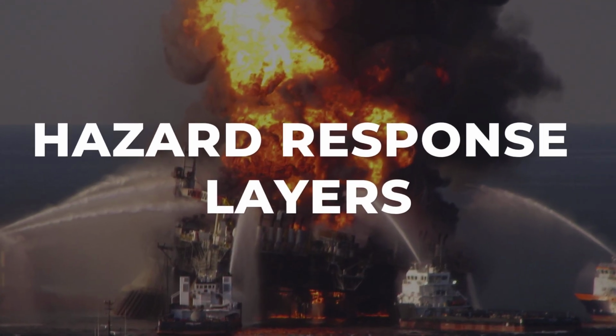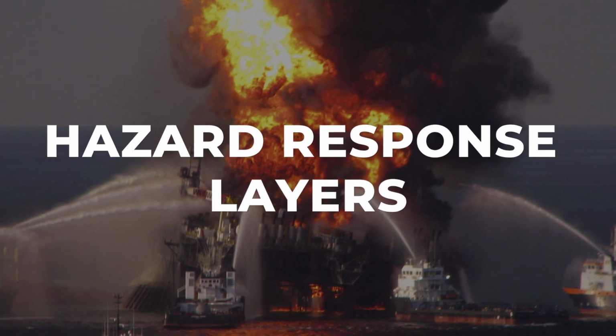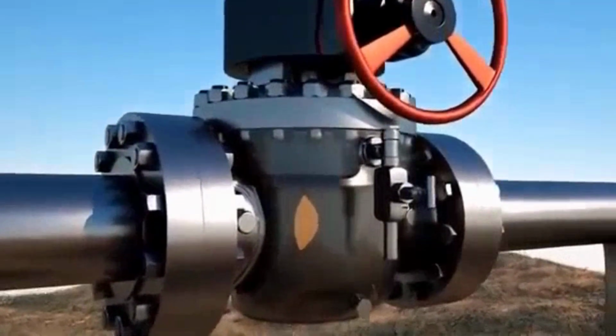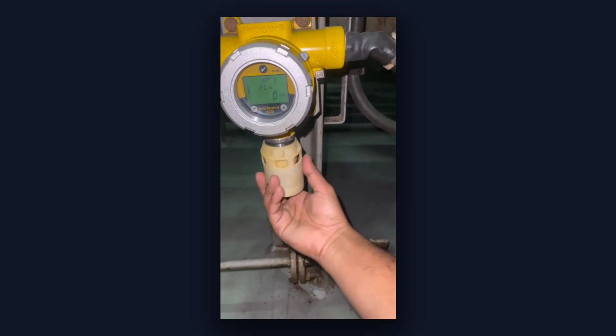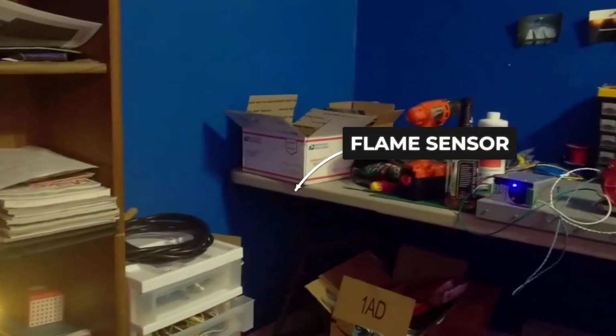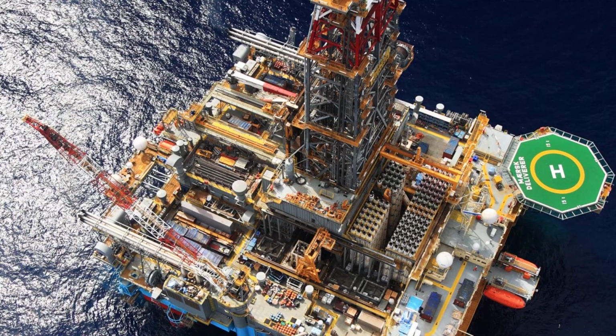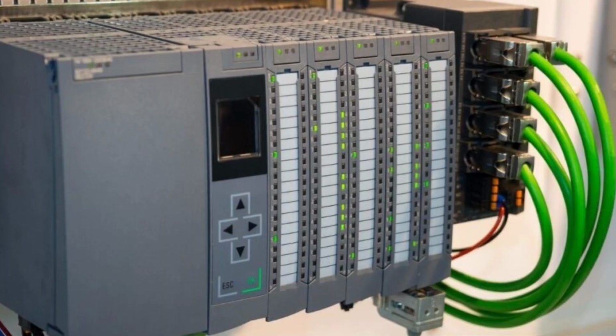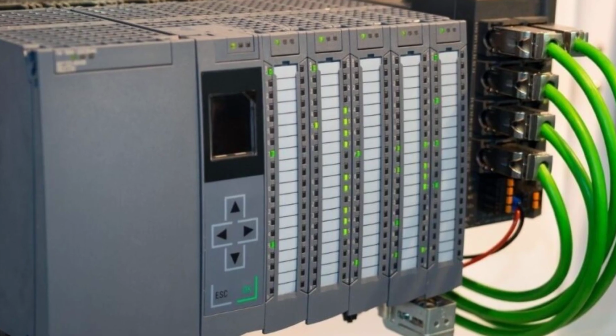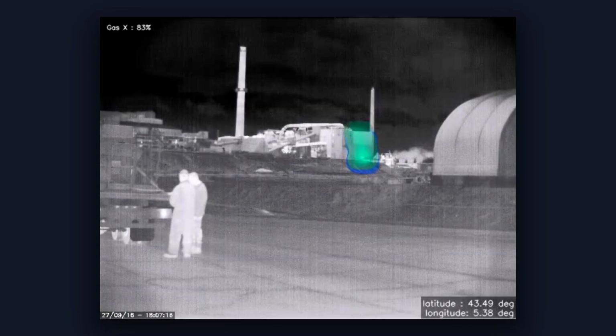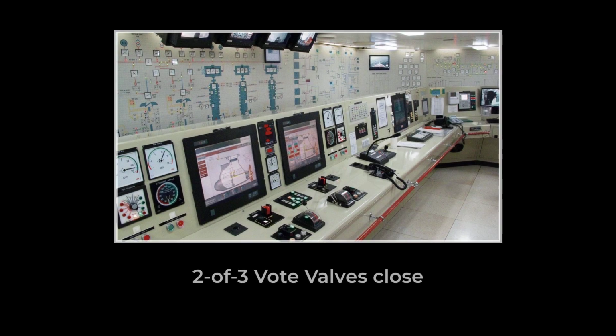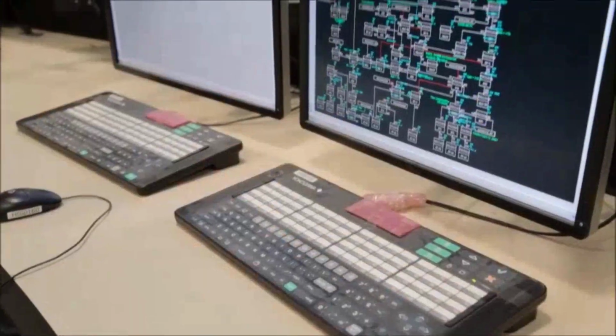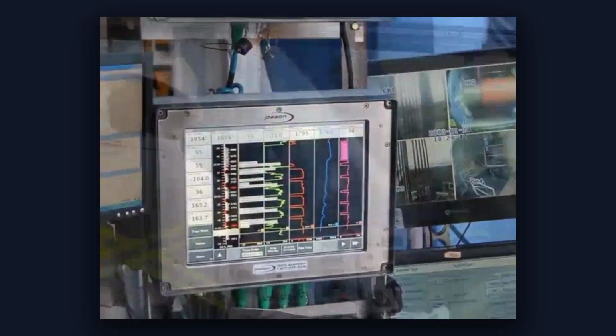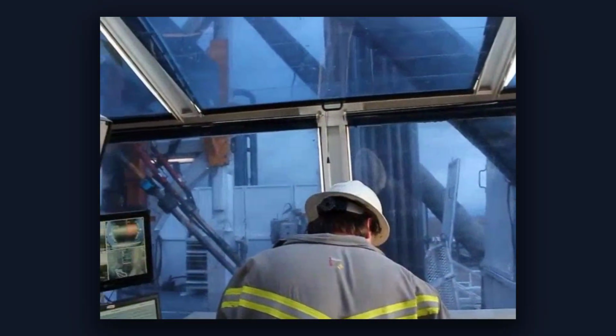Invisible threats, gas leaks, vapor clouds, and sudden fire are the hazards that offshore safety systems are built to contain. The first line of defense is a dense network of sensors, each tuned to detect hydrocarbons, hydrogen sulfide, or open flame. These sensors are distributed across 4 independent safety zones, with each zone feeding data to its own local controller. When a sensor detects a dangerous concentration, it does not act alone. The system uses a 2 out of 3 voting logic, so at least 2 sensors must agree before the alarm escalates. This reduces false positives, but ensures a real event triggers an immediate response.